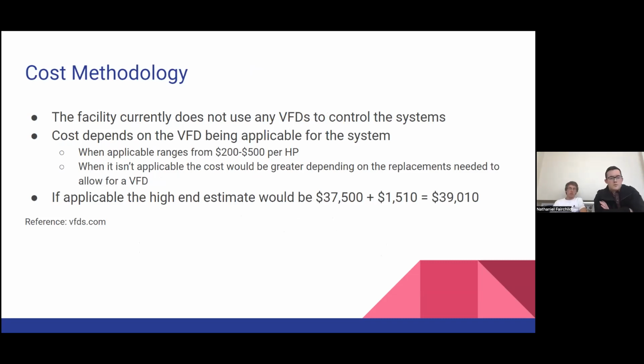Alrighty, and so the cost methodology for the facility is that currently they don't have many VFDs on their systems. They have a few for their cooling tower fans, but for these other systems, they don't actually have anything. So the implementation costs will definitely be dependent upon if the VFD is applicable for that system. And as Marla stated, the minimum is $200 per horsepower, with the maximum being about $500 per horsepower unit. And if the VFD isn't applicable to the system, there would definitely be a greater cost because you have to replace the system and make it applicable for that.